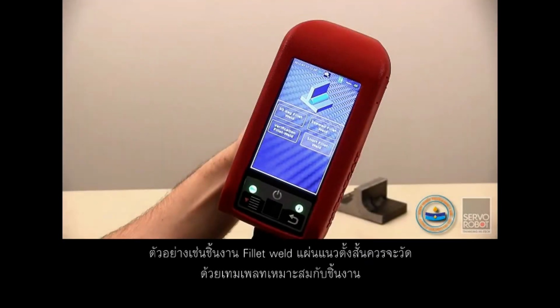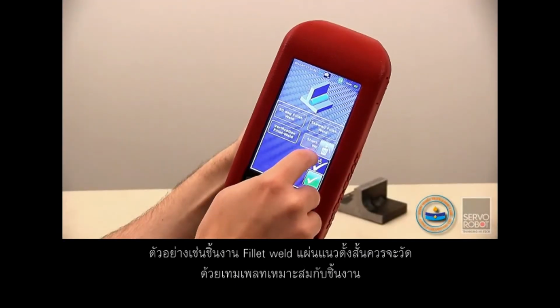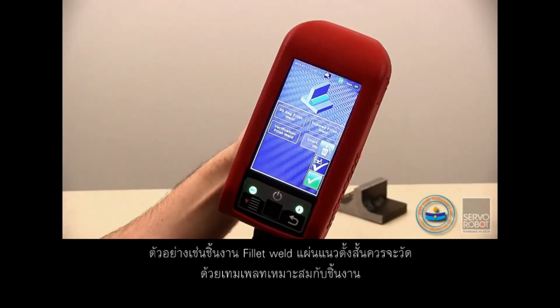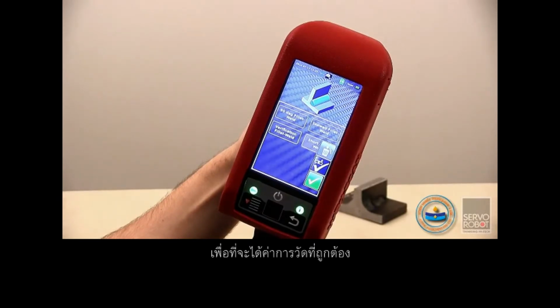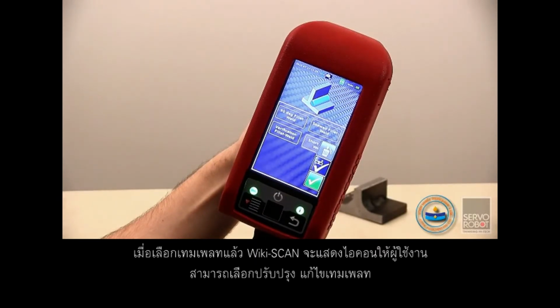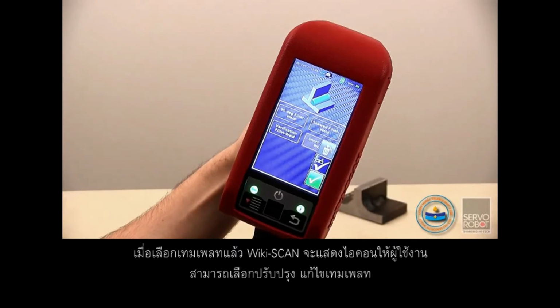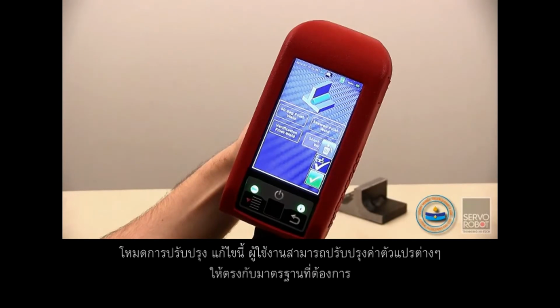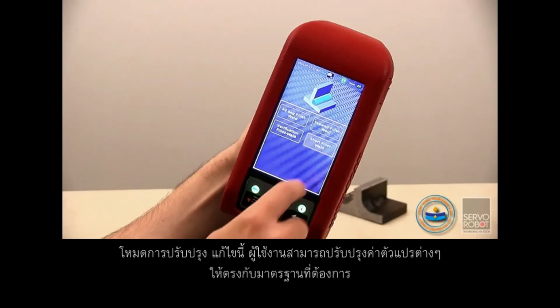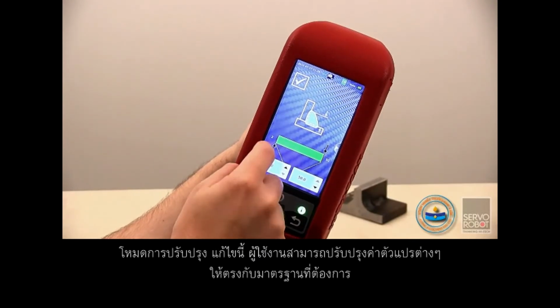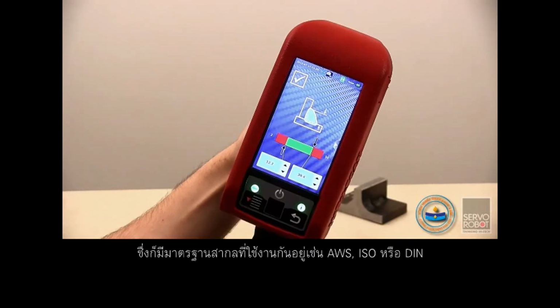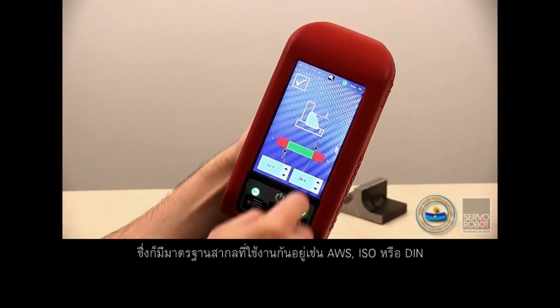For example, a fillet with short side walls should be measured using the corresponding template in order to obtain the most accurate measurements. Once a template is selected, the WiKi-Scan prompts for a confirmation or the user's edition of the template. The edition mode is there so that the user can configure the WiKi-Scan based on their own custom quality standards or on official standards such as AWS, ISO, or DIN.